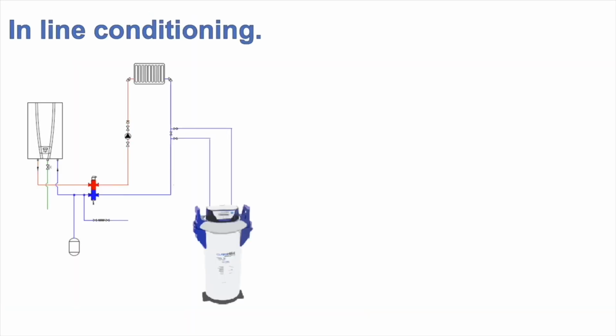Inline conditioning. So we might want to do inline conditioning when we've got an existing system. We want to improve the water quality of an existing system. It might not be preferable to drain and refill this system, or you might have an underfloor heating system. It's particularly good for underfloor heating systems. You don't need to dump the water that's already in the loops. It could be quite hard to get rid of them. The same process applies, as in you need to clean the system, you need to make sure that the water within the system's not got heavily dosed with chemicals.